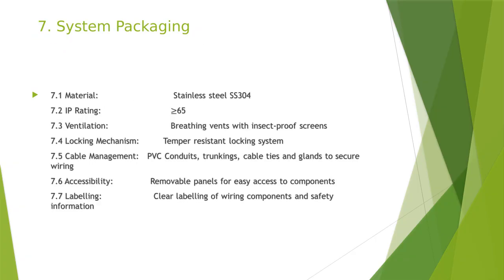Let's move on to the next stage, which is system packaging. The material should be stainless steel SS304 and an IP rating of greater than or equal to 65. And for ventilation, we've got breathing vents with insect-proof screens and a tamper-resistant locking system. And on cable management, we've got PVC conduit trunkings, cable ties, and glands to secure wiring. And there must be clear labeling of wiring components and safety information.